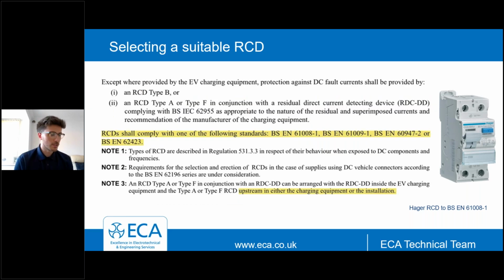Now, sticking with this regulation, there's some further detail that accompanies it. So it tells us that RCDs shall comply with one of the following standards. This is BS EN 61008-1, BS EN 61009-1, or BS EN 60947-2, or BS EN 62423. So this regulation is quite clear.